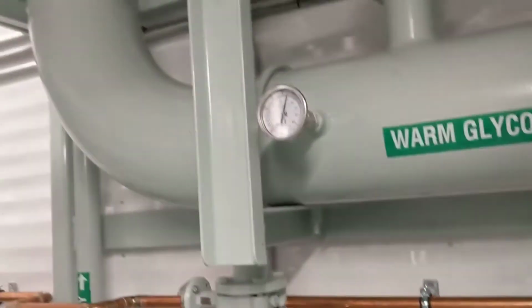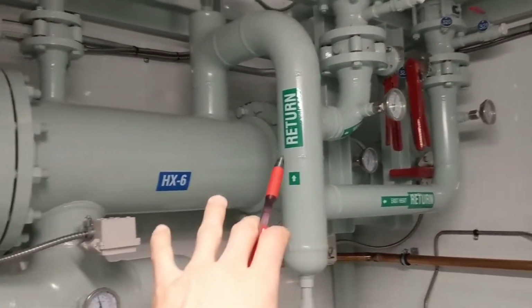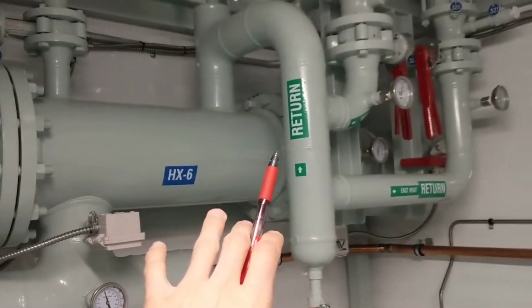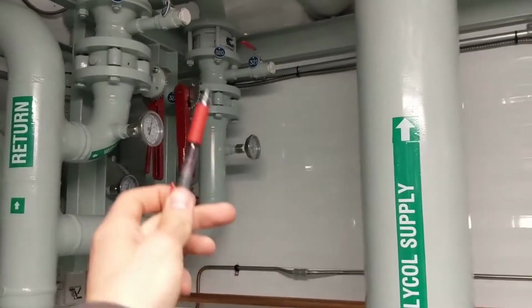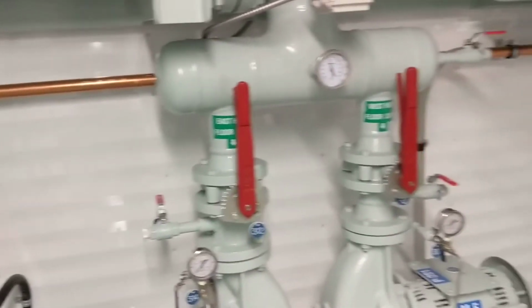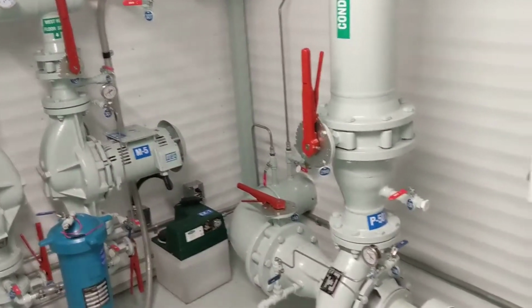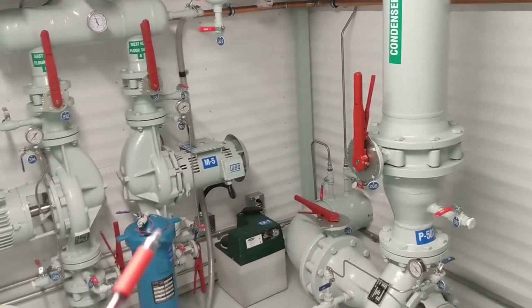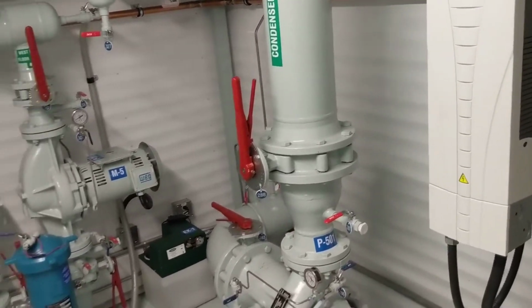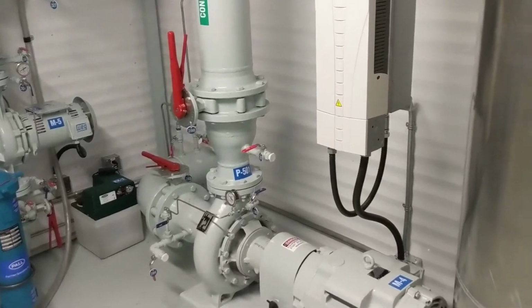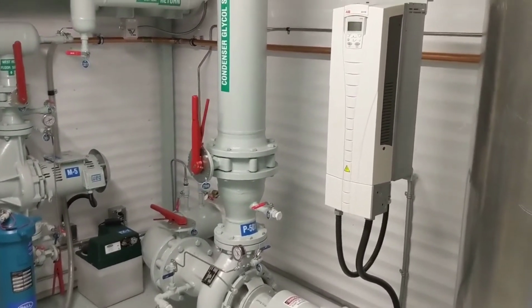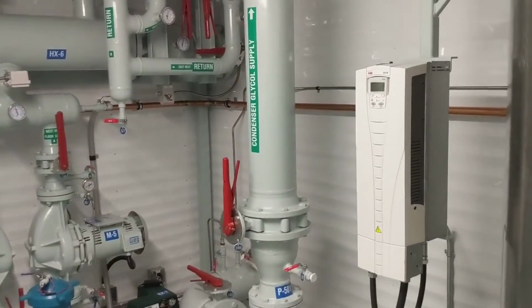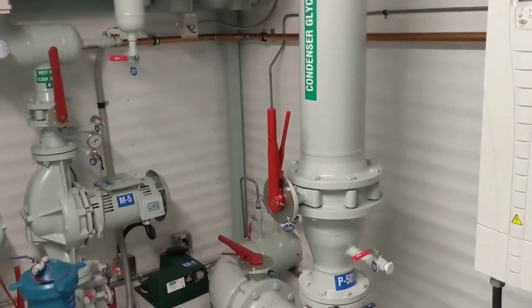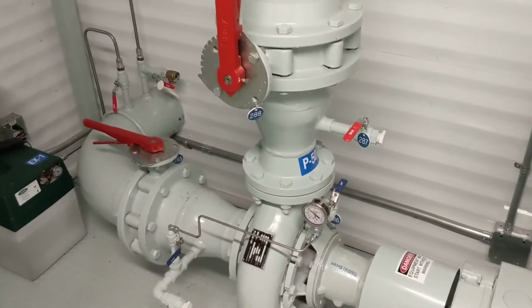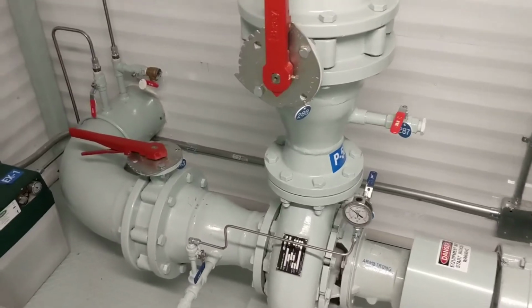The glycol is feeding from here. It's going along, and as it gives up some of its heat to the snowmelt pit and the warm floors, it then goes outside and up through the fluid cooler. So what the fluid cooler is, basically, it looks like a giant air conditioner, and then it's got a whole bunch of small tubes running through it and fins on it, and it moves air through it, and occasionally will spray a water mist onto it in order to cool down the glycol, and it ramps its fans up and down accordingly to give the glycol temperature that Ultimate spec'd it to.